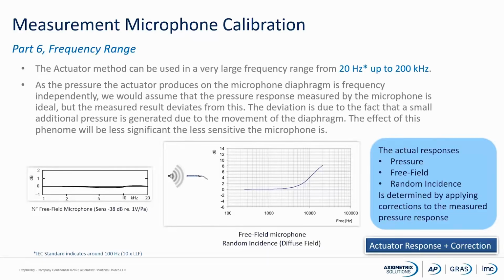But when the diaphragm is moving and you have this plate, the actuator, on top of it, there will be a certain resistance between the actuator and the diaphragm itself. So it will give a little deviation at higher frequencies. So you actually have to make a little compensation even for a pressure microphone. But this compensation is very, very small, in the neighborhood of maximum 0.2 dB. And the uncertainty for an electrostatic actuator principle is normally 0.4, 0.5 dB, depending, again, on the frequencies.